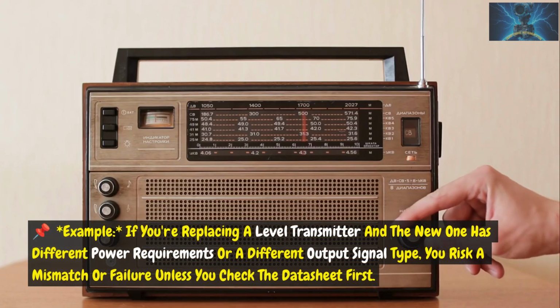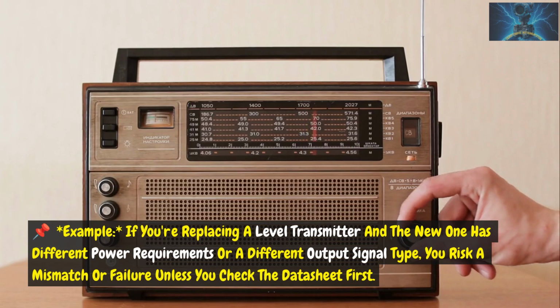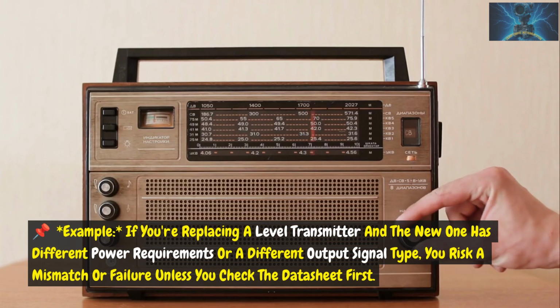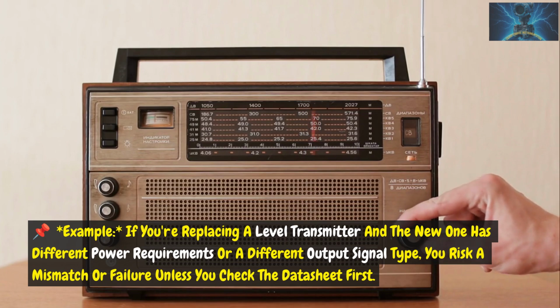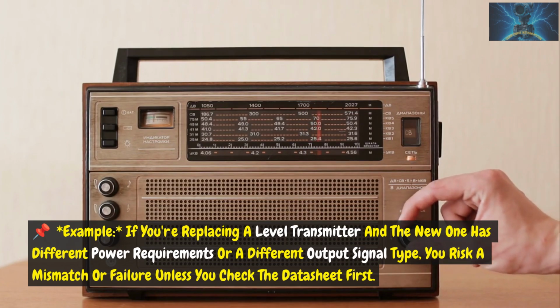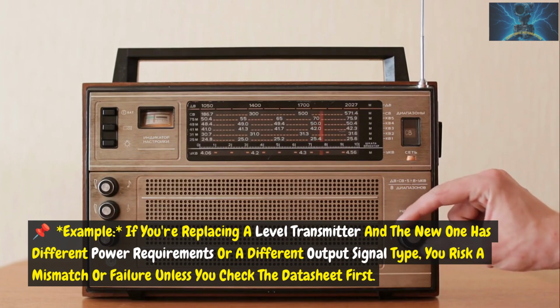For example, if you're replacing a level transmitter and the new one has different power requirements or a different output signal type, you risk a mismatch or failure unless you check the datasheet first.